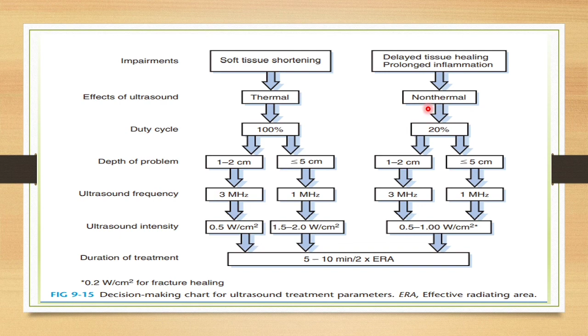And the treatment time will be 5 to 10 minutes depending upon the effective radiating area. If the treatment area is twice the effective radiating area, we can use 5 to 10 minutes. It depends upon the area as well as the effects, whether you want a thermal effect or a non-thermal effect. If you want thermal effects, you should go for continuous ultrasound. If you don't need a thermal effect, and want just non-thermal effects, you can go for pulsed ultrasound. So by this, we are concluding this video on ultrasound.